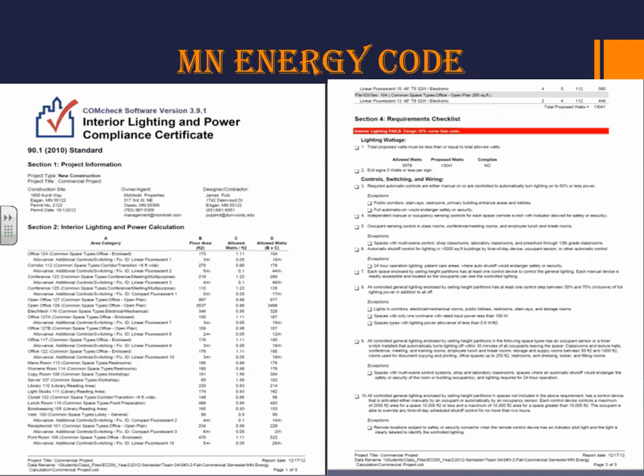Being solo, I kind of ran out of time to change everything out. To get it to pass, I probably would have had to drop a lamp out of some of the fixtures. Instead of using three, drop down to two, or drop down from 4 to 3 or 4 to 2 to get it to pass.